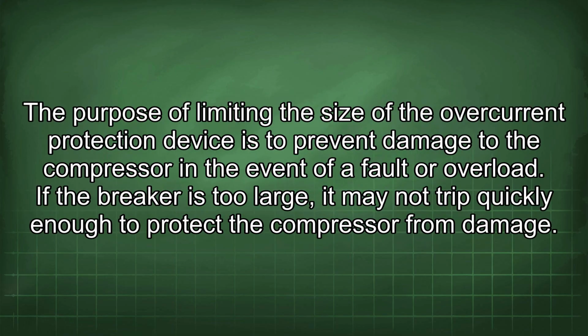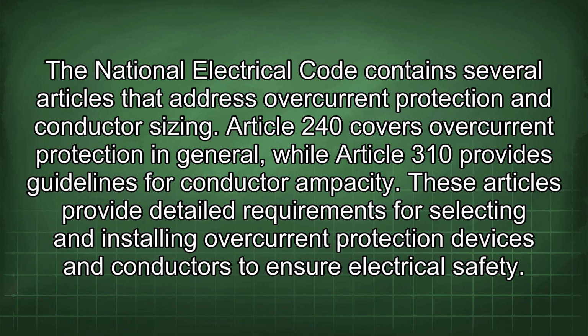The purpose of limiting the size of the overcurrent protection device is to prevent damage to the compressor in the event of a fault or overload. If the breaker is too large, it may not trip quickly enough to protect the compressor from damage. The National Electrical Code contains several articles that address overcurrent protection and conductor sizing. Article 240 covers overcurrent protection in general, while Article 310 provides guidelines for conductor ampacity. These articles provide detailed requirements for selecting and installing overcurrent protection devices and conductors to ensure electrical safety.